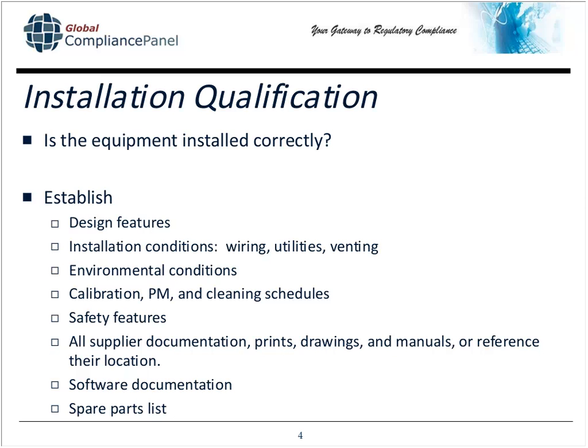You also want to make sure that any supplier documentation, including prints and drawings, manuals, anything you receive from them, you've got to have that. In your IQ document, because this is all going to be documented, you're going to reference their location. Most of the time, the supplier documentation will reside with the production manager, for example, any sort of production management or supervisor. You want to make sure on your IQ document you reference the location of that documentation. All of these things, the design features, installation conditions, environmental conditions, et cetera, will need to be documented on your IQ document. Any sort of software documentation, if there's software involved in the running of the equipment, more so is this software programmable by the user as opposed to having some sort of resident memory.